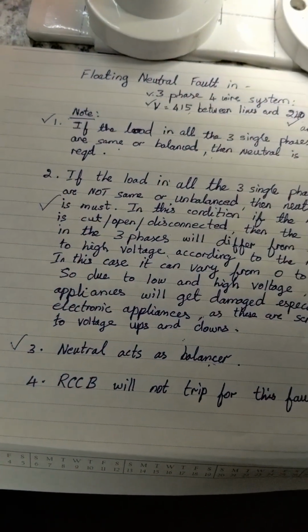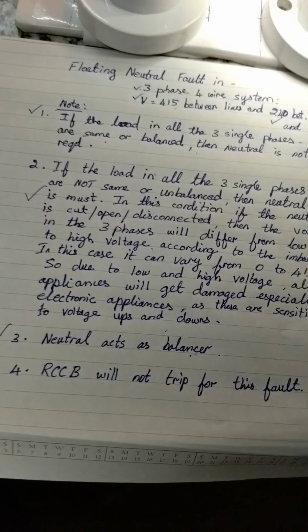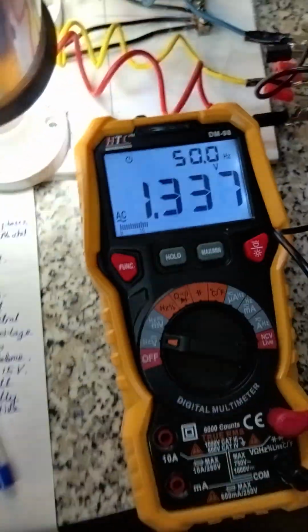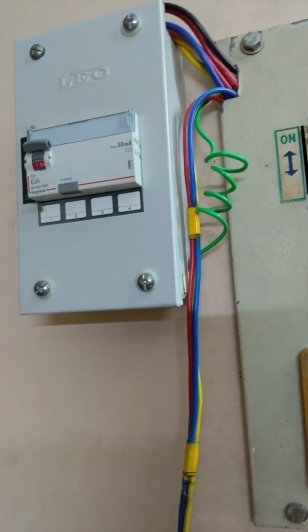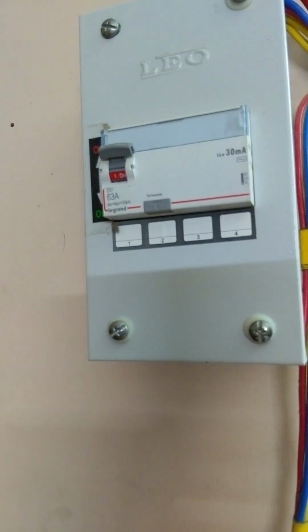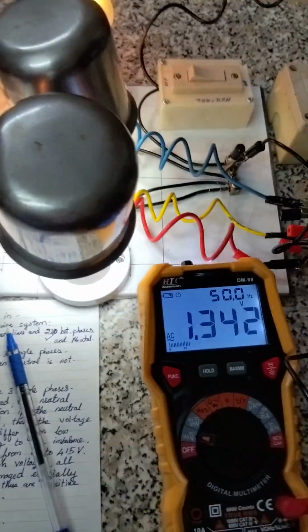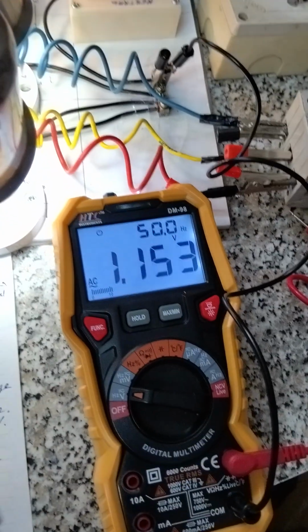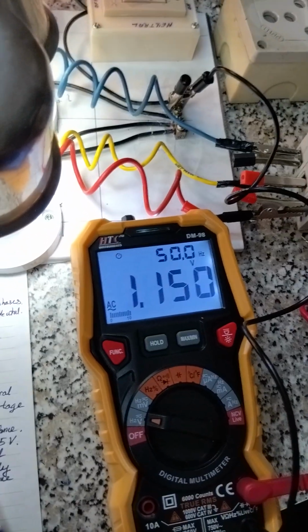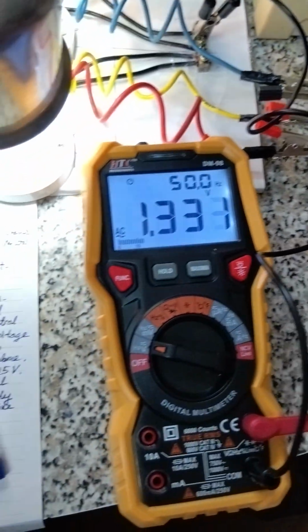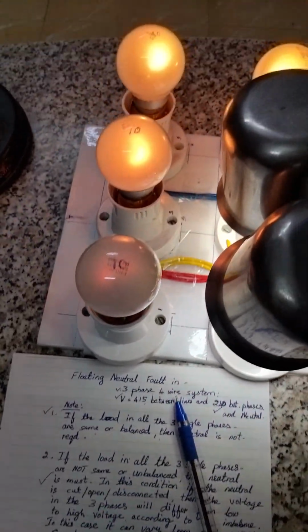The fourth point, RCCB will not trip for this fault. Now we are conducting this experiment through an RCCB protected supply. It has not tripped. So if any person or YouTuber tells that RCCB will safeguard from neutral, floating neutral fault, it is a lie. They are lying. Don't believe them. So we have seen this also.